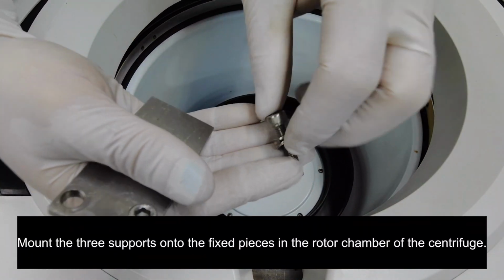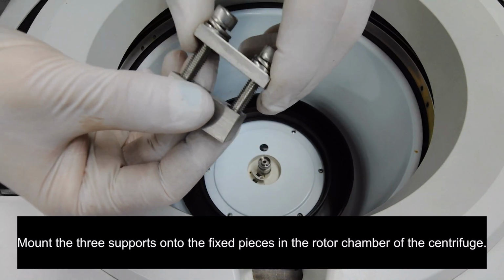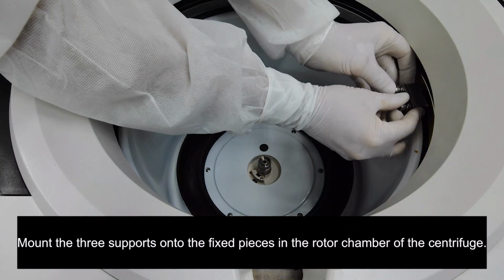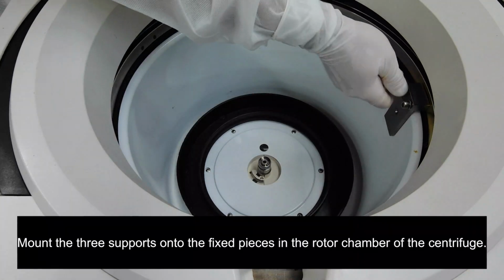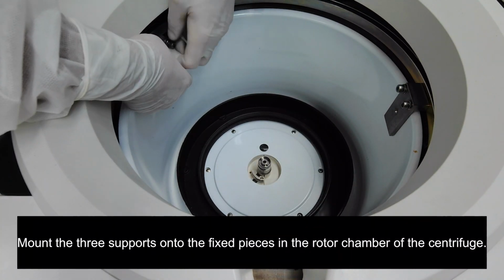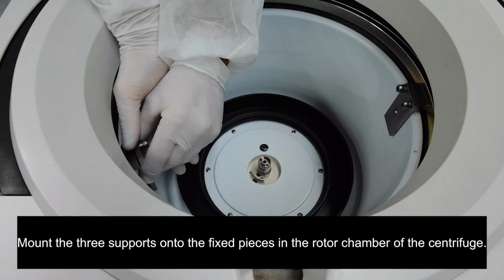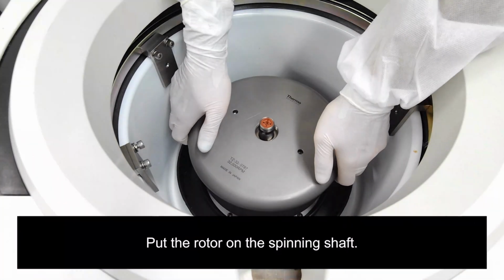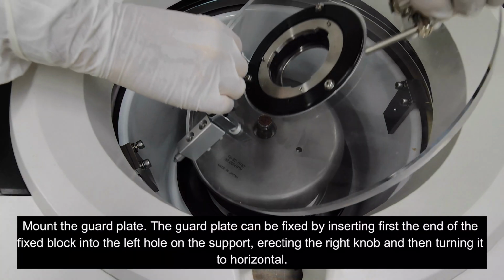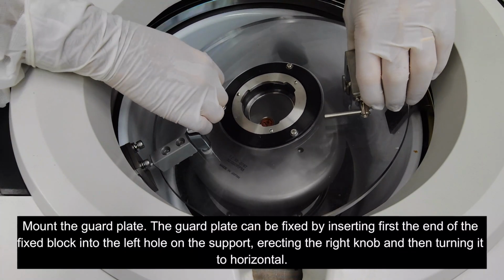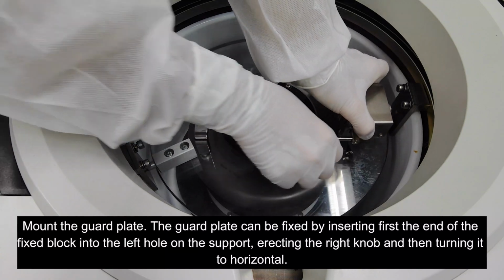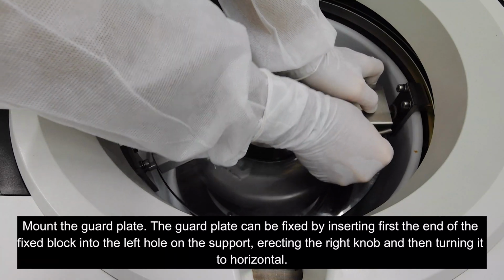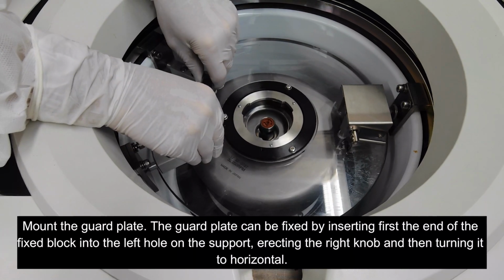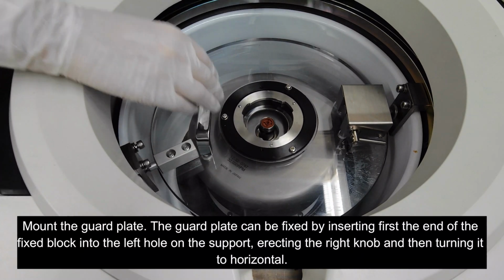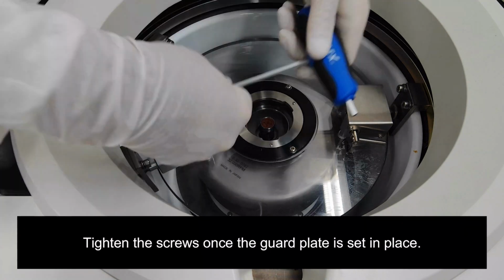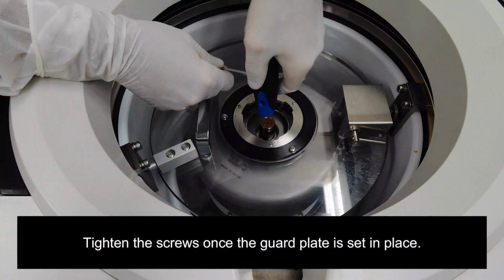Mount the 3 supports onto the fixed pieces in the rotor chamber of the centrifuge. Put the rotor on the spinning shaft. Mount the guard plate. The guard plate can be fixed by inserting first the end of the fixed block into the left hole on the support, erecting the right knob and then turning it to the horizontal. Tighten the screws once the guard plate is set in place.